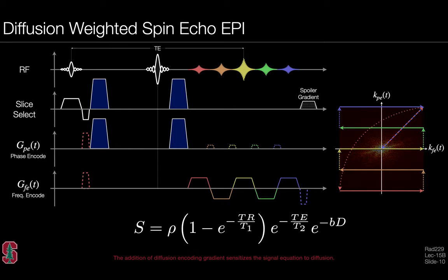Diffusion gradients can be applied on any axis—x, y, z, the readout axis, or any linear combination of the three. For diffusion tensor experiments, it is important to design different linear combinations to sample diffusion along different directions: gradients on the slice-select axis sample diffusion in that direction, gradients on the phase-encode axis sample diffusion there, and linear combinations sample diagonal directions. Exploring these directions further is the topic of the next lecture.